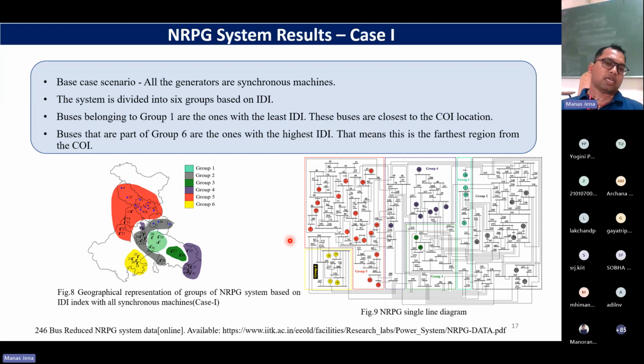Using the previous slide, we calculated the inertia distribution for each and every bus, and then we grouped them into different areas, group 1 to group 6. Group 1, this green color, is the area or the generators which are staying closer to the center of inertia, and group 6 is the machines which are away from the center of inertia. So this is the base case. What we are expecting is, if I now replace some of these generators with inverter based resources, there will be a redistribution of inertia across buses, and redistribution of inertia distribution will lead to redistribution of these groupings.